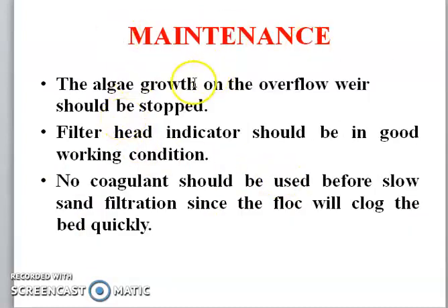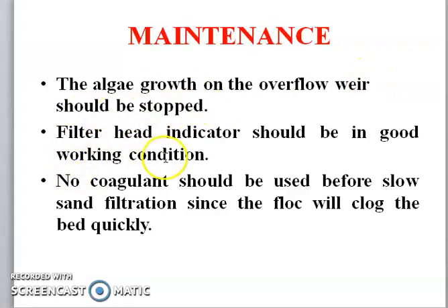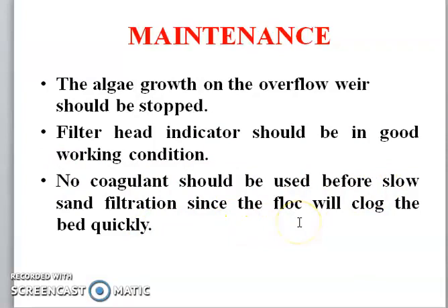Maintenance is very important. Algae growth on the overflow weir should be stopped. The filter head indicator should be in good working condition. No coagulant should be used before the slow sand filter, since the flocs will clog the bed quickly.